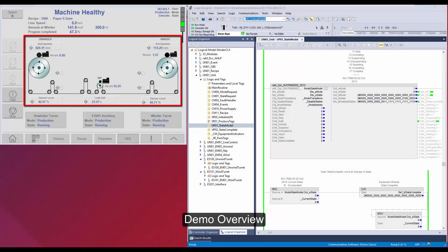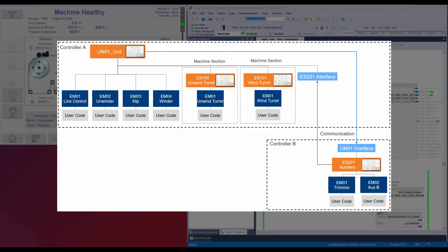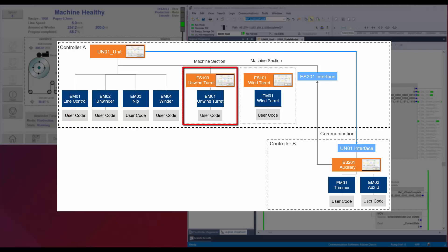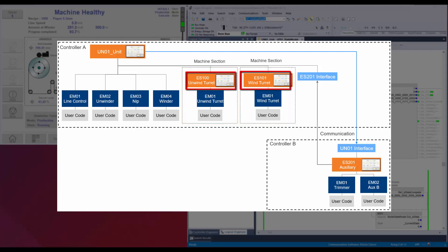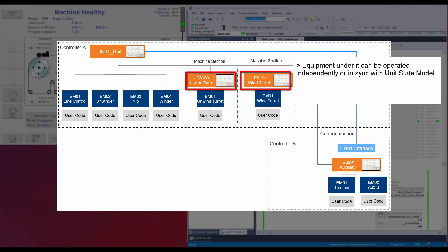I have a winder-unwinder application demo. The application is divided into four sections. The main machine has unwinder, NIP, and winder devices. These equipment modules are directly connected with the unit state model. The next two sections are roll changeover turret for winder and unwinder. These sections have their own equipment supervisor with its own state model. An equipment supervisor enables the equipment under it to be operated independent of the unit state model, or run in sync with the unit state model.